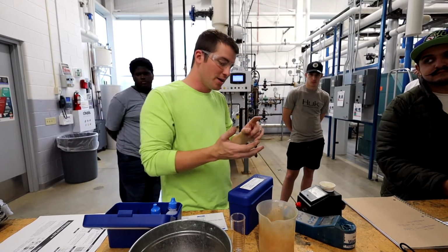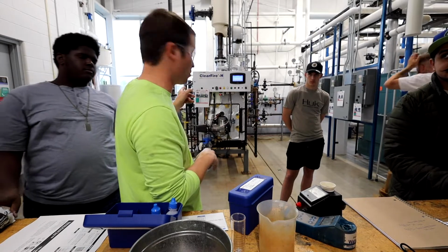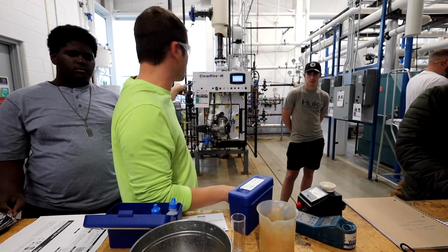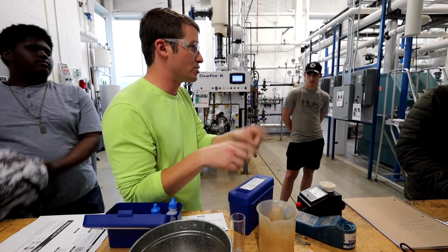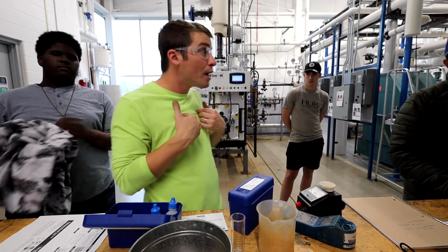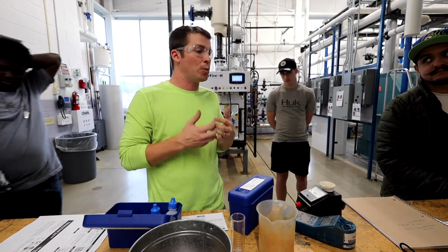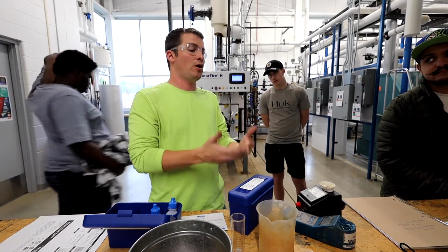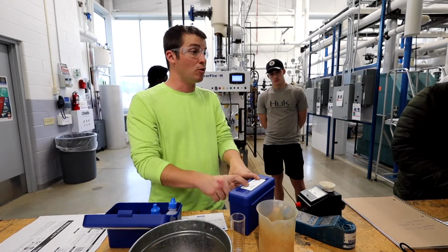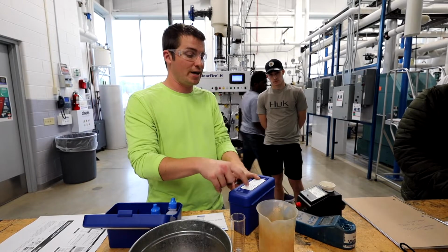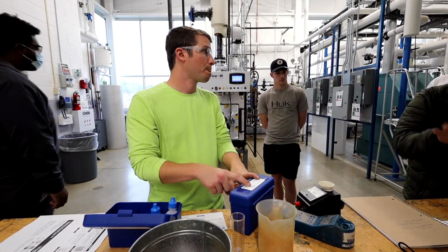It's more work, it's more confusing, and again, in a program like this, truthfully, you can't control it. There's nothing you can go do right now that's gonna change this reading. I don't have you run it because you're not gonna do anything. I run it because I do wanna make sure we have enough O alkalinity in the boiler, but I normally don't have customers run it that aren't running RO water because they're not adding a chemical to directly impact this. If you're running a boiler that has RO water, you're directly adding something to impact this, then I would tell you, you gotta run it. If you're not running RO, don't even worry about it.